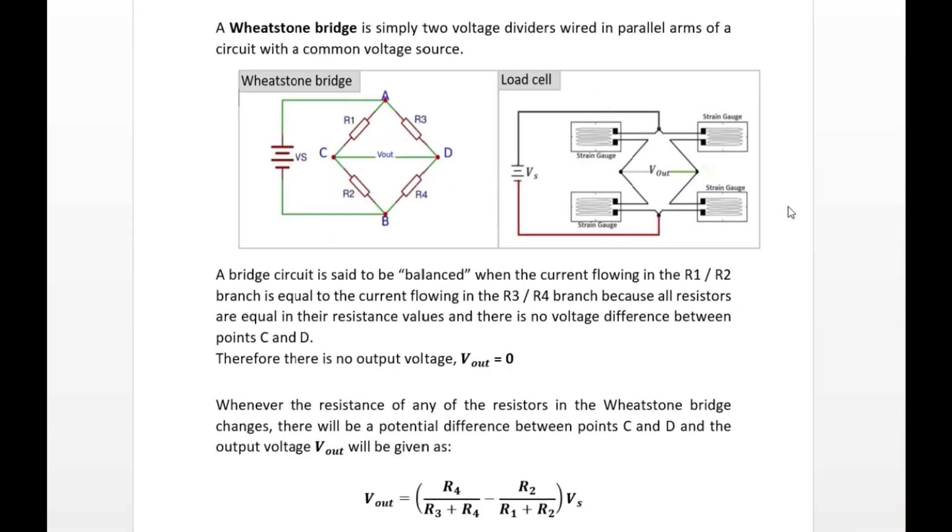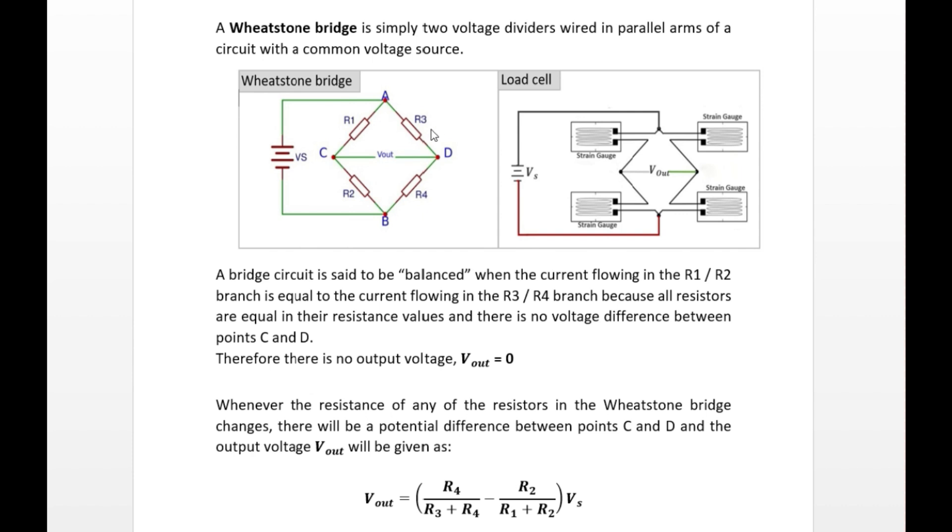Next, I will talk about Wheatstone Bridge. This is one of the basic principles of electronics, so I won't go too much into details of how the Wheatstone Bridge works. I'll just be showing the relationship between this bridge and the load cell. This is the general circuit of Wheatstone Bridge. It is simply two voltage dividers wired in parallel with a common voltage source. If you compare these two diagrams here, this is the setup for our four-wire bar type strain gauge cell. In the load cell, instead of the resistors, we are going to use strain gauges. So we have four strain gauges representing the four resistors of the Wheatstone Bridge. Normally when the Wheatstone Bridge is balanced, it means all the resistors are equal. In that case, the current flowing through the branches A, C, and B, and the other branch A, D, and B, the current is equal. Therefore, there is no potential difference between point C and D, and the output voltage will be zero. However, when the resistance of any of these resistors changes, that means there is going to be a potential difference at this point. In that case, the output voltage will be given by this equation.